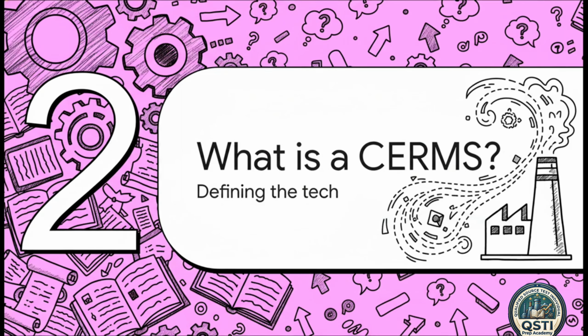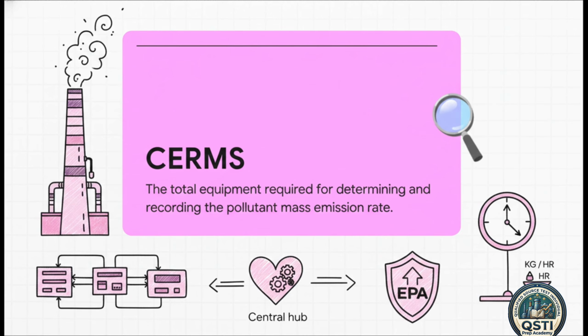All right, moving into Section 2. What is a CERMS? Let's translate some of that government speak and define the actual piece of technology we're evaluating today. So, CERMS. It stands for a Continuous Emission Rate Monitoring System. The absolute key phrase you want to focus on here is total equipment. We aren't just talking about a single lonely probe shoved into a smokestack. No, we're evaluating the entire interconnected system required to determine and record the pollutant mass emission rate. And crucially, it measures this in terms of mass per unit of time, like kilograms per hour. This system is literally the central hub. It's the heart of stationary source environmental compliance.